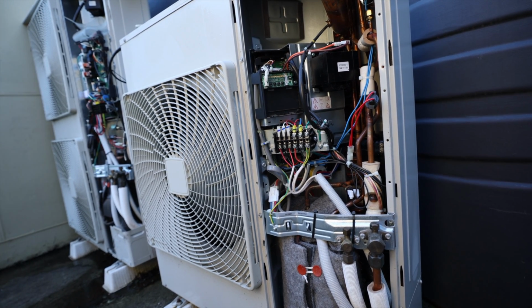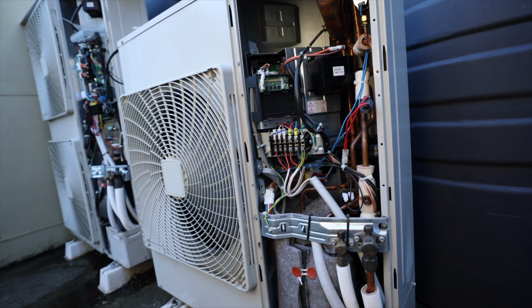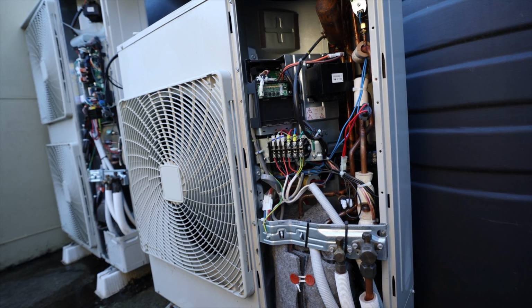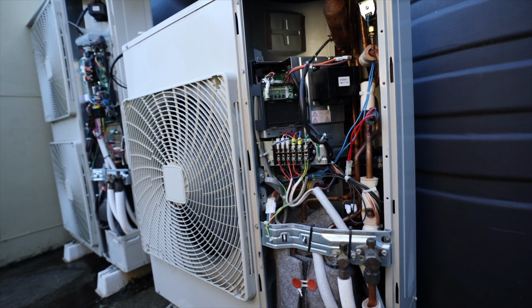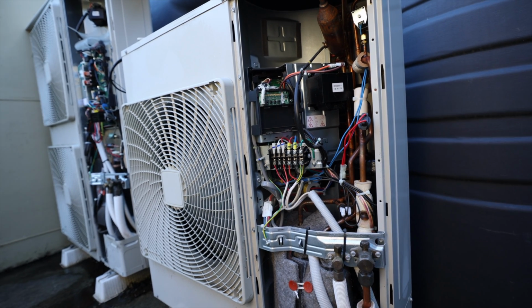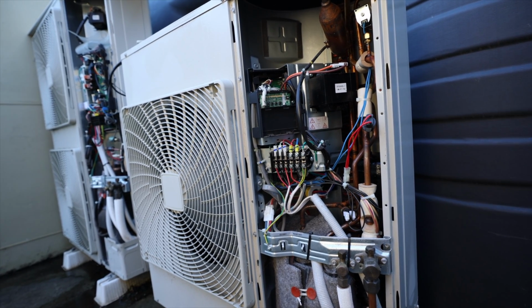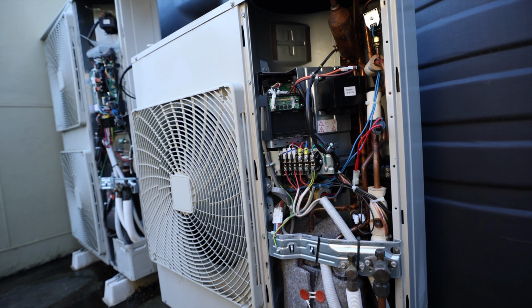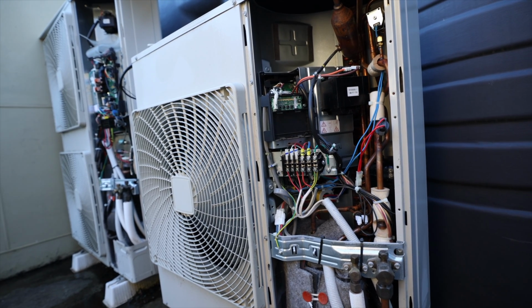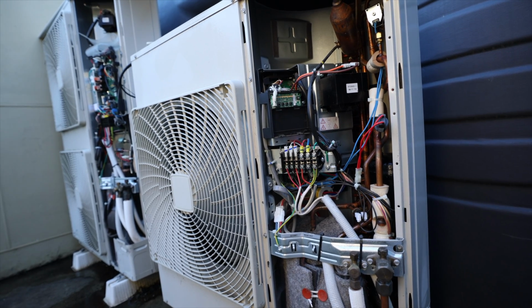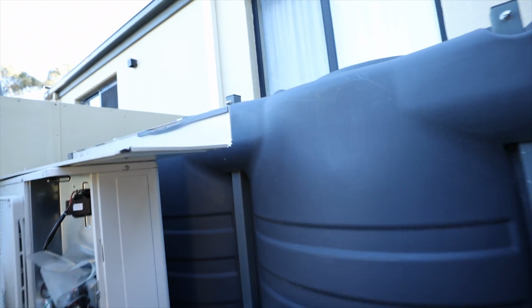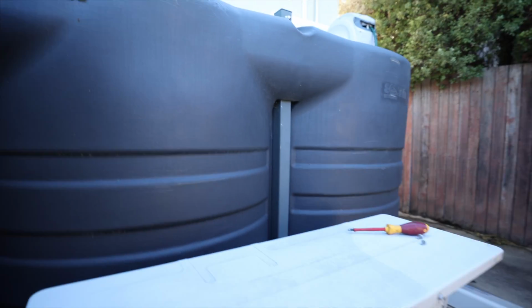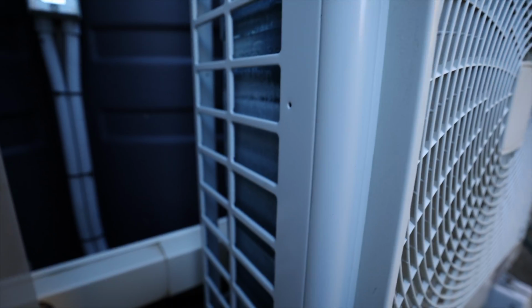So for that time, you're not getting any heat in the house. It's a negative. If your system has 20 kilowatts and it's off for a quarter of the time, you've only got 15 kilowatts to play with now. The next thing is that it has less capacity at -5, so there's less heat in the air, and you've lost a few more kilowatts, so then you're down to even less.